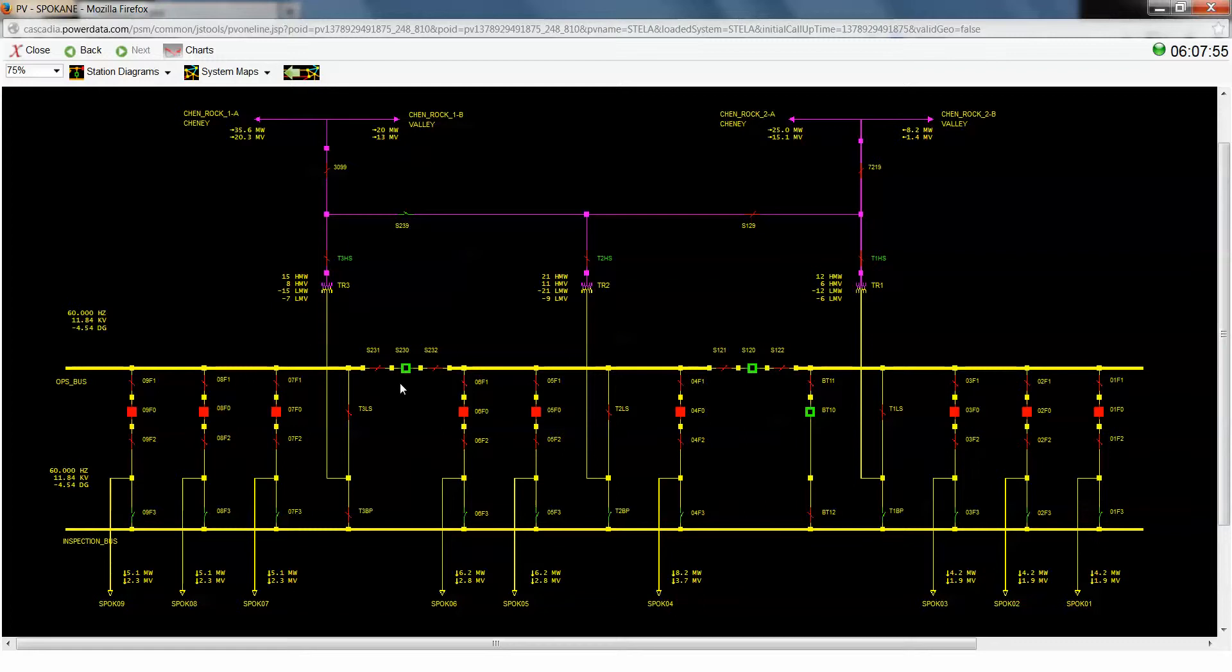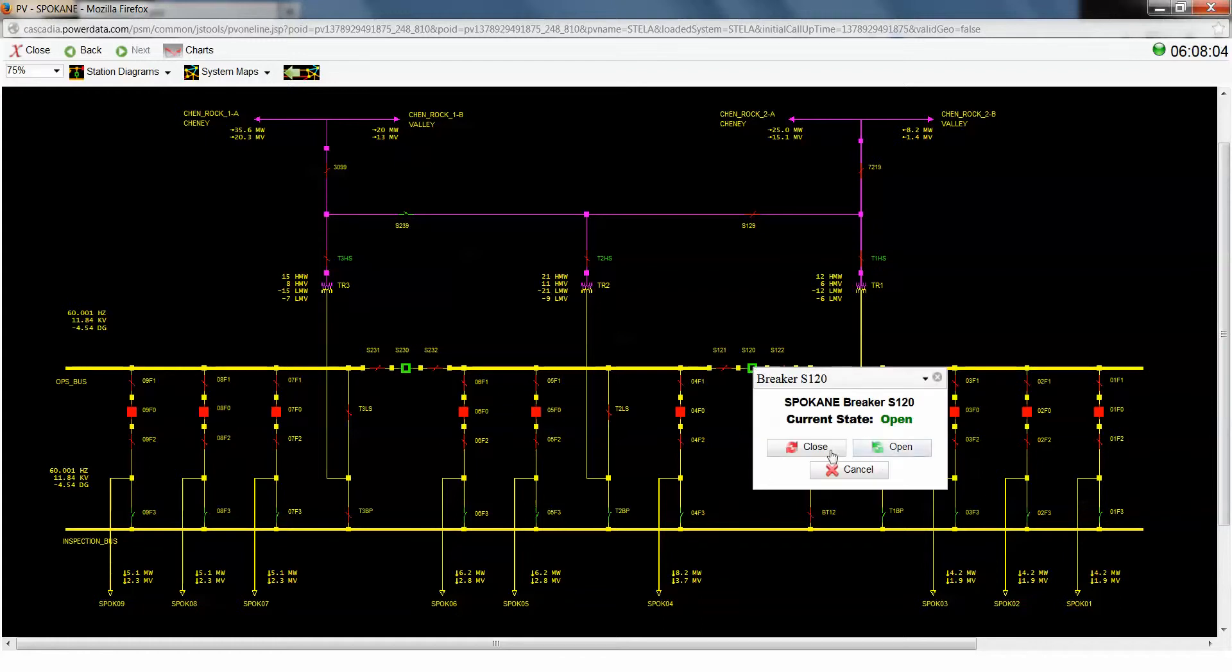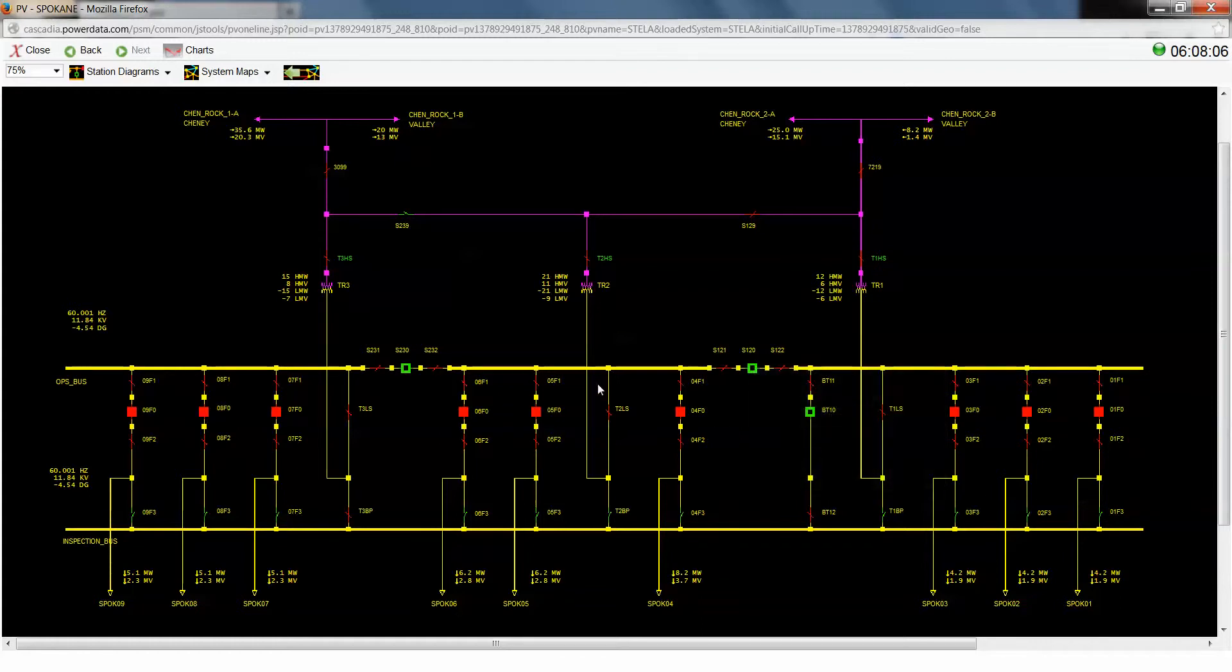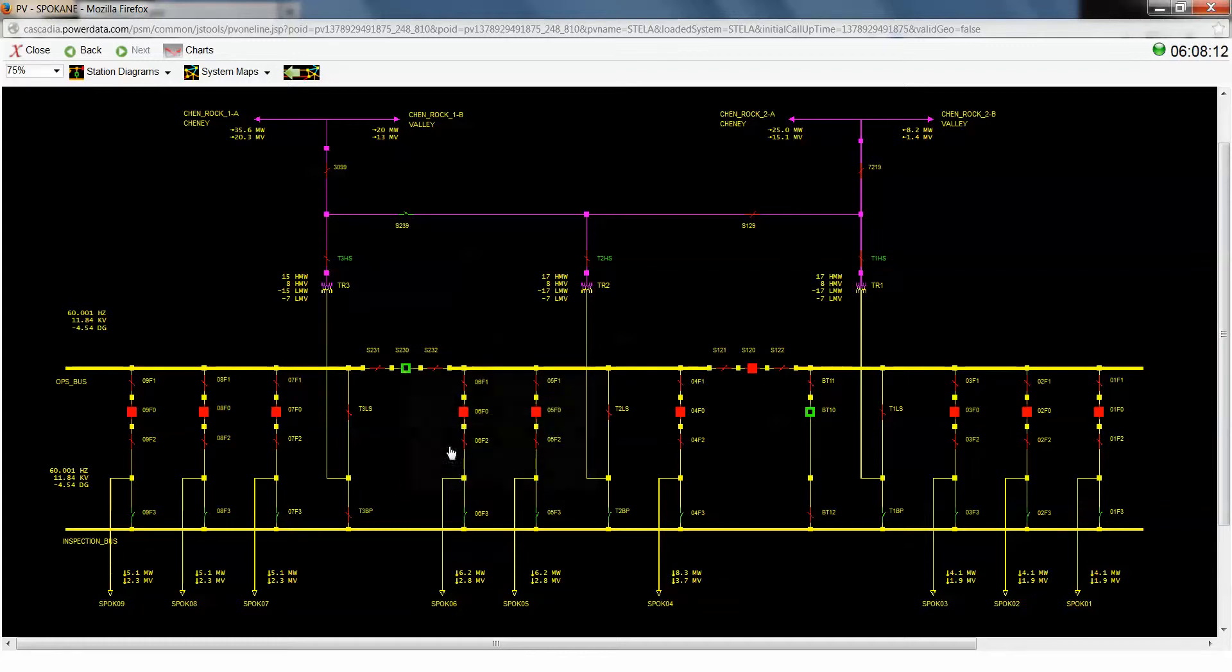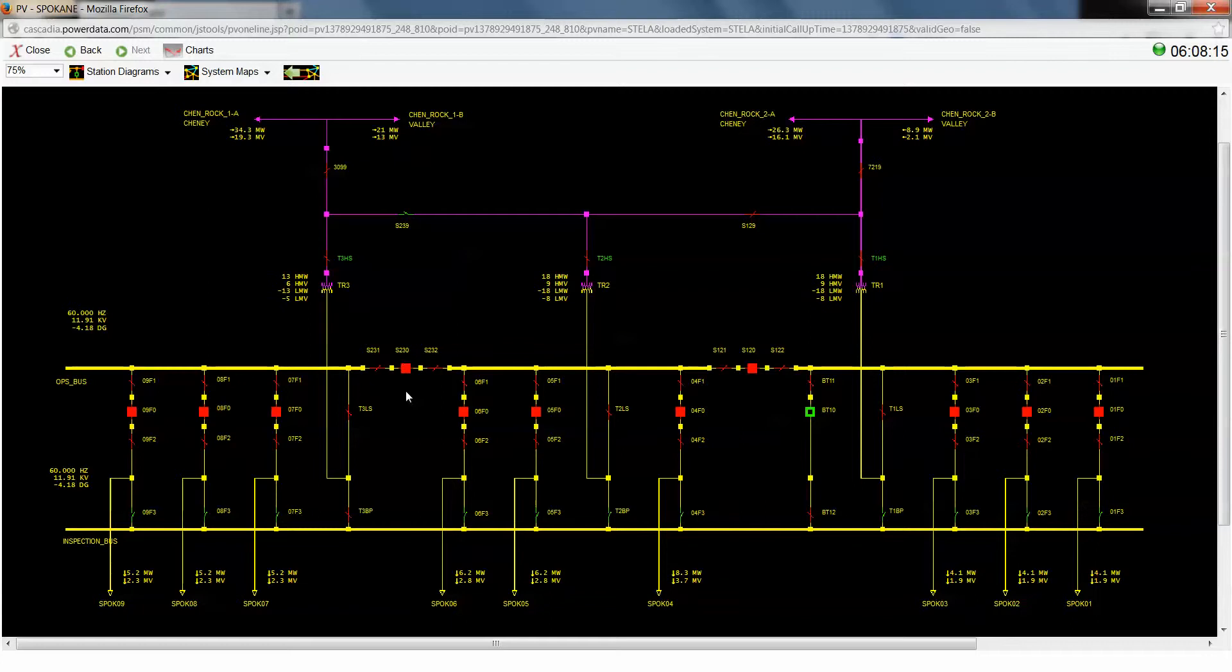Okay, so the next thing that we're going to do is we're going to want to equalize the loading across these transformers. So we're going to need to close these two section breakers. Number 120, see that breaker come closed. And number 230. And we'll see that breaker come closed and we'll see the loading shift around on our transformers one and two.